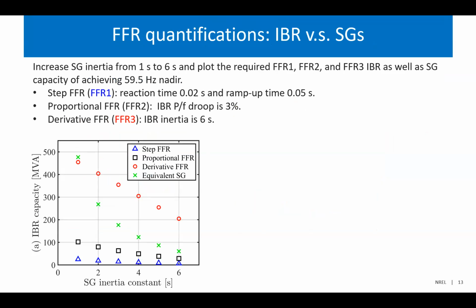And next, at last, I think you probably still wonder, because this is a very popular question, how much capacity of the FFR is equivalent to how much capacity of the synchronous generator? I have to say that's a really challenging question, but we also try to use this analytical method to help us understand at least the relationship between those different types of FFRs. So we go back to our simple two-generator system you saw before, and we decrease the inertia of the entire system, to mimic a system with a higher penetration level of renewables, where inertia could be lower. And meanwhile, we trigger the same event and test how much capacity of the IBR can achieve the same frequency nadir. Here we set it at 59.5 Hertz.